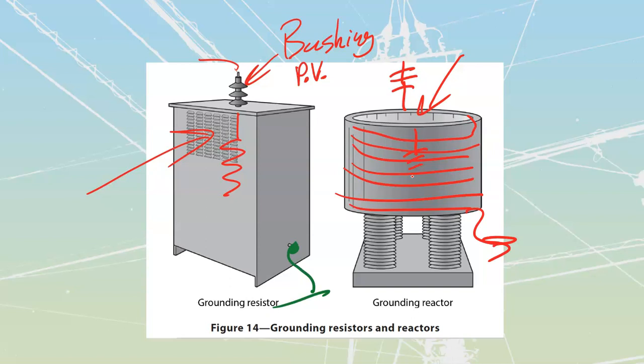The manufacturer is usually going to make sure that these things come pre-terminated with a bonding jumper. So there's going to be a bonding jumper inside of the transformer that is going to go over from its X0 point, and they're also going to have another bonding jumper that's going to go over to the actual can itself. Remember that we're only ever allowed to ground down a system a single time. So it's going to be up to you as an electrician to determine whether or not you need to remove this grounding jumper over here. Sometimes you'll leave them in.